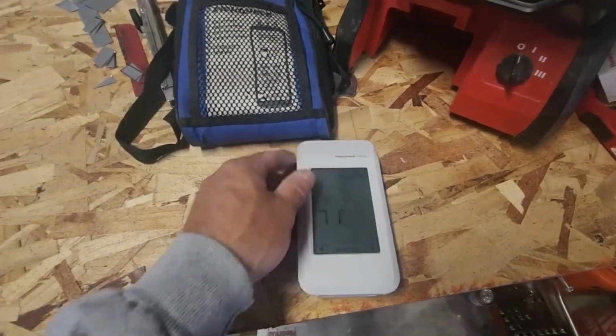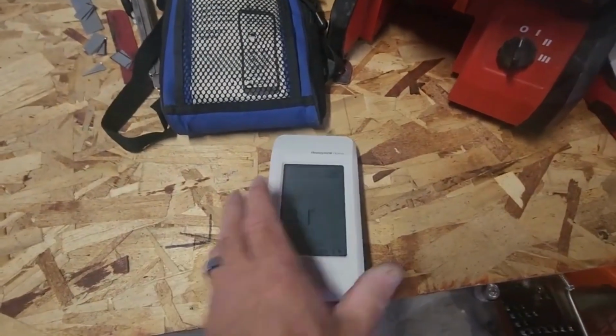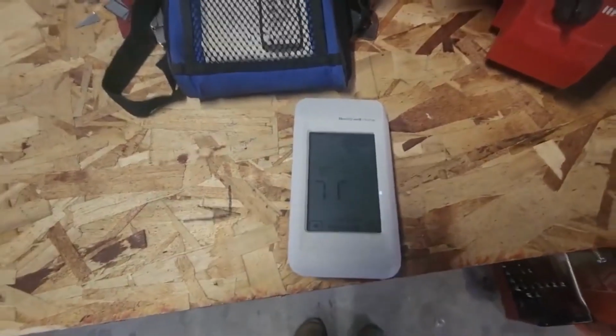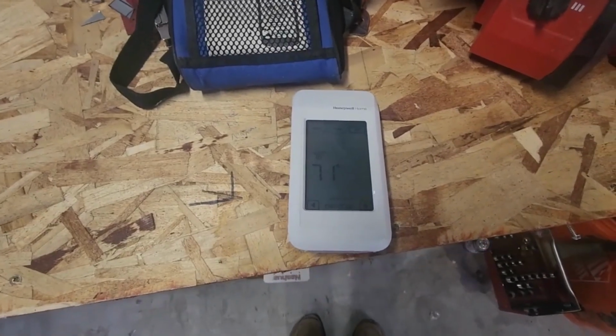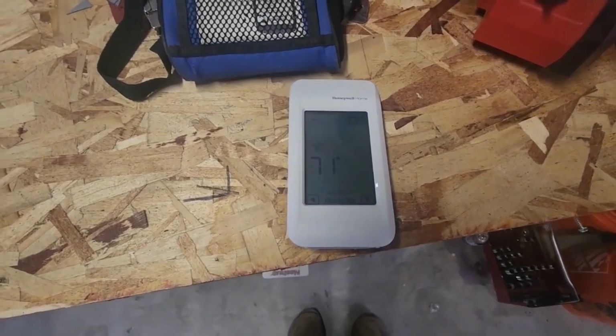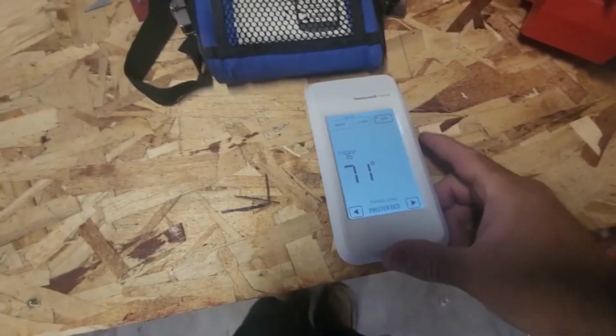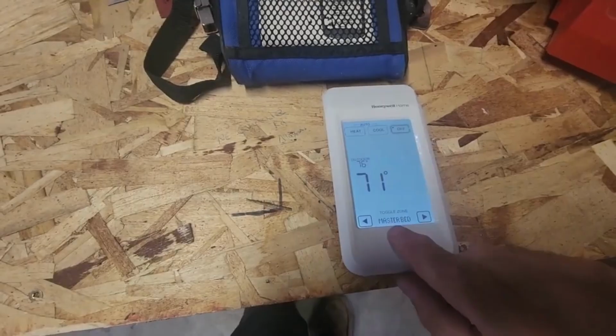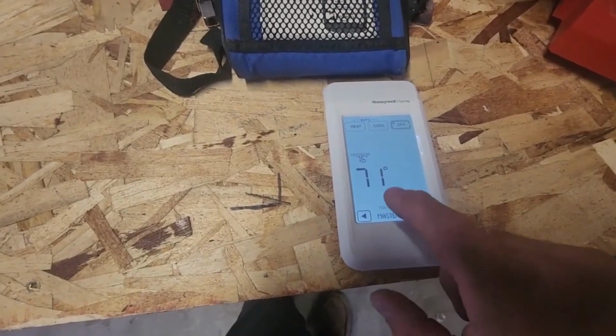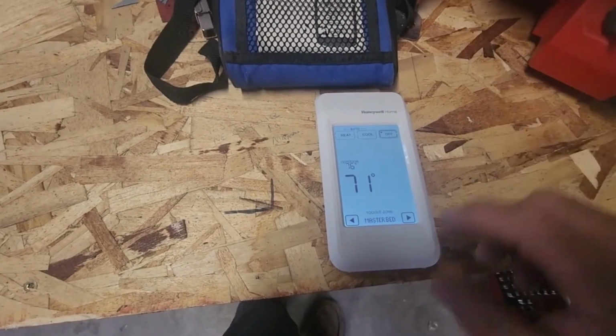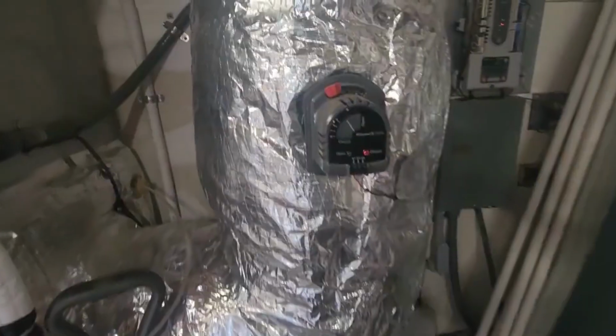is I have this portable comfort control here, and I can just toggle between zones out here. I don't even have to go in the house. I wanted to do it by the zone panel, but it only stays in test mode for a few minutes, I'm realizing. So let's go ahead. Master bed, that's my downstairs. I'm going to flip that one on, and then turn the upstairs off, and let's see what that does to our static.